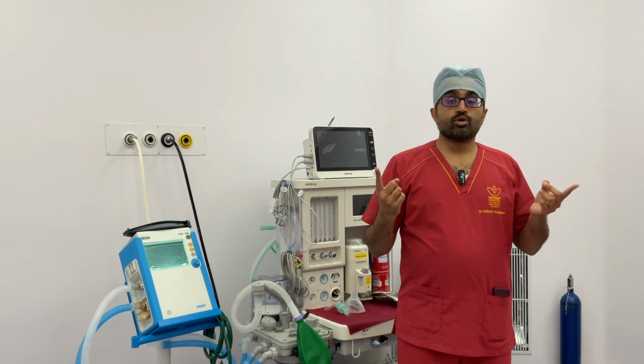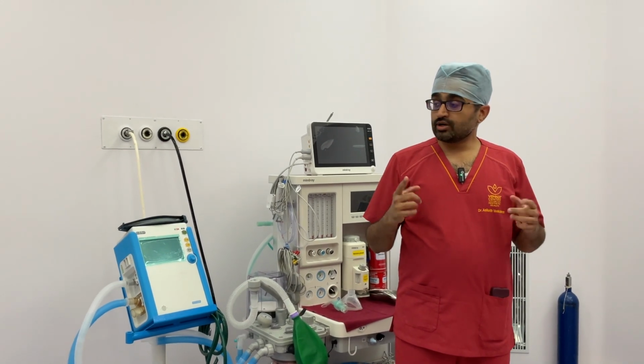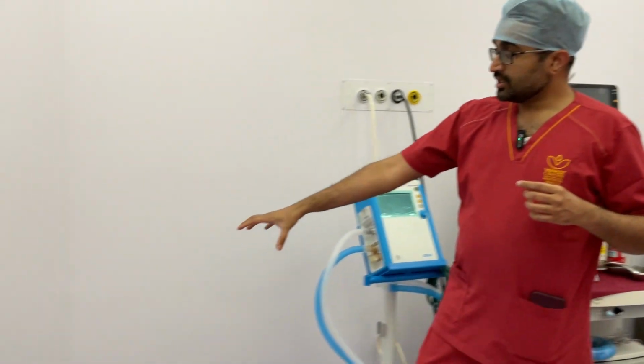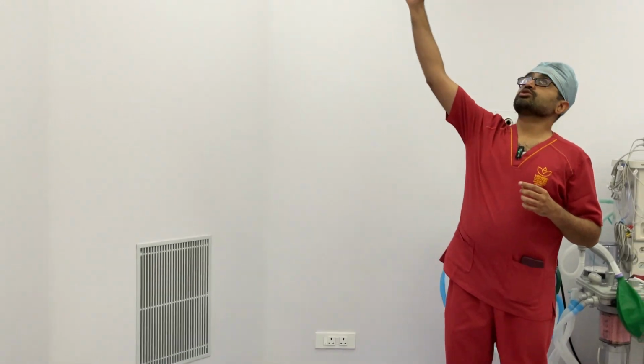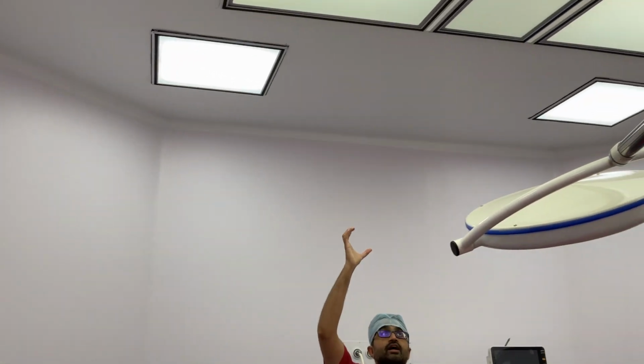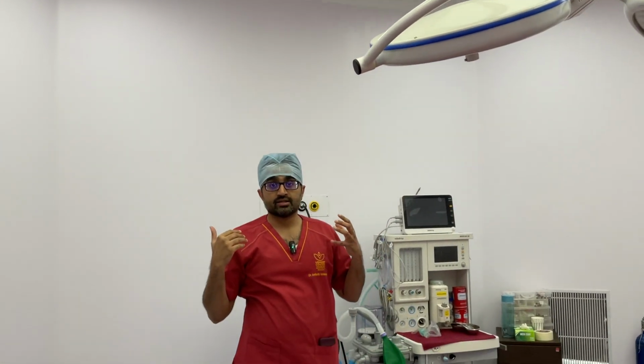This is a fully modular OT with laminar flow. What that means is you can see these ducts here. Air is taken in through the duct, it goes into the roof and it is filtered, and through a HEPA filter it comes back in. So this is what is called a modular OT, wherein the air is continuously circulated and filtered to ensure that there is no bacteria or viruses in the air. These are all the precautions we go through to make sure that you are safe during your surgery.